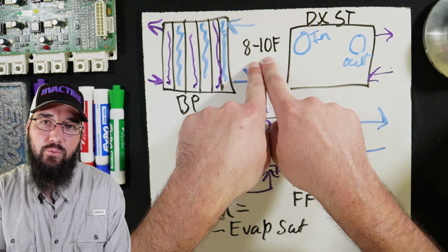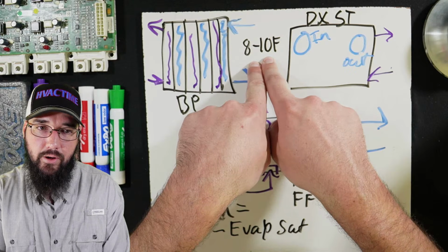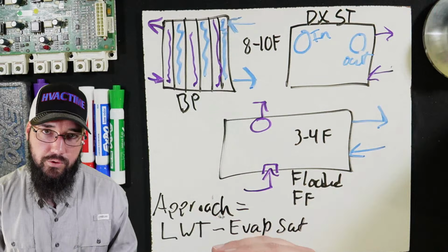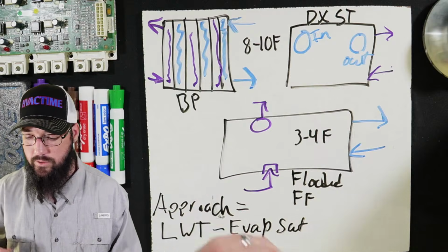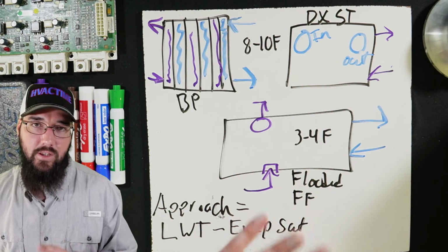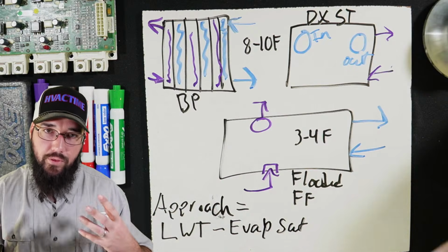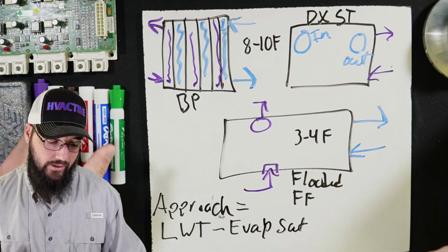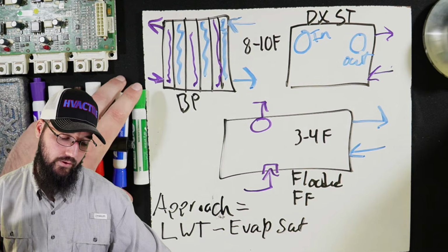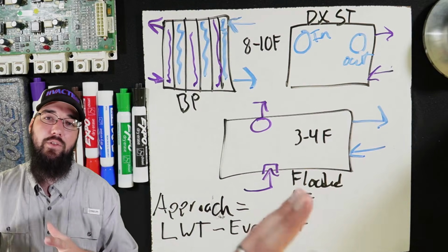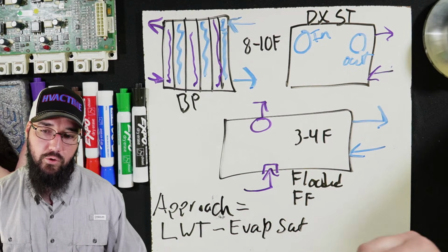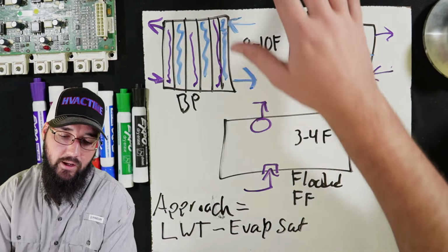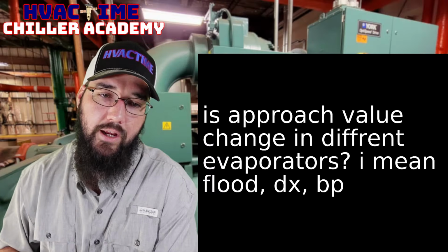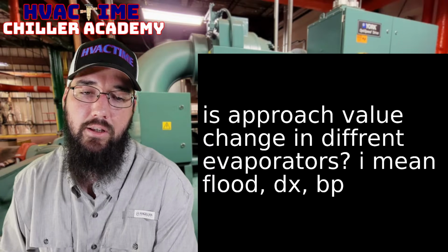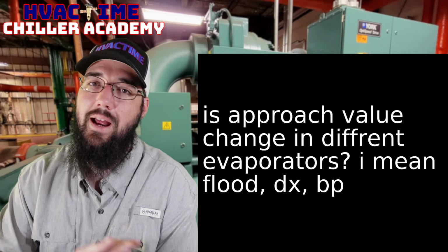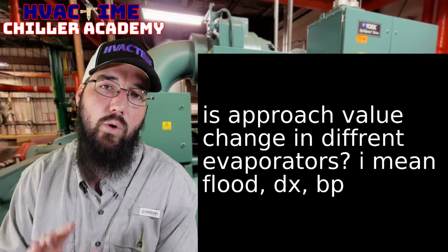So as we increase load on the evaporator, approach temperature increases with it. We decrease load, approach temperature should decrease with it. Same exact correlation here. It's the exact same concept, just applied in a different way. So we have to think about this stuff, and this is part of what makes data analysis so tricky as a service technician, because we have to think about all these various relationships and how everything is tracking and moving together. This is why what we do is very complicated. Anyway, that's the high level answer to is approach value change in different evaporators between flooded, DX and brazed plate. That's a very high level review of what that means and why it functions that way.